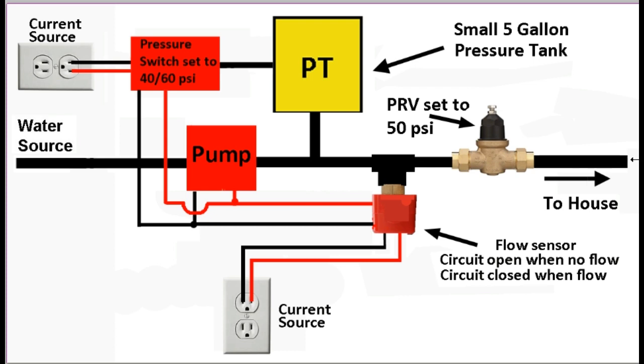With this system, you get 50 psi all the time. There's no fluctuation at the beginning of the run. And there's no problem with the dribble flow, so the pressure tank will fill up quickly. And you can choose to have a small pressure tank. There's no reason not to have a small pressure tank, because the system will go on every time you use water, just like a cycle stop valve. It won't cycle, but it will go on every time you use water.